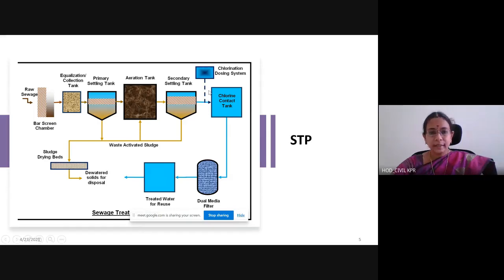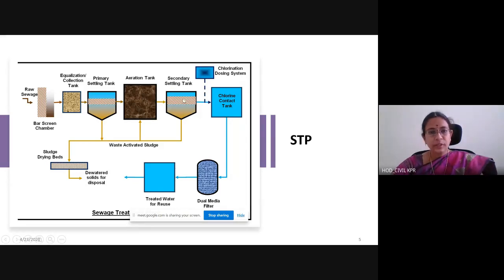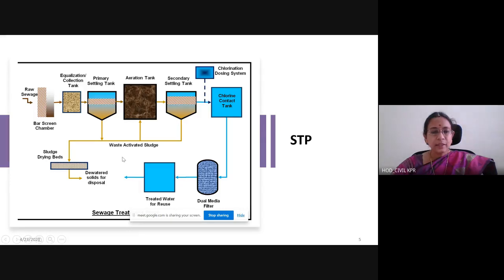Then it is moved to the secondary settling tank. Here, some particles that might not have settled — because of their size or discrete characteristics — when aeration is given, these particles may join together and form a floc. So larger-sized particles are also settled here in the secondary settling tank. After settlement, the debris or settled particles are collected together and it is called activated sludge.